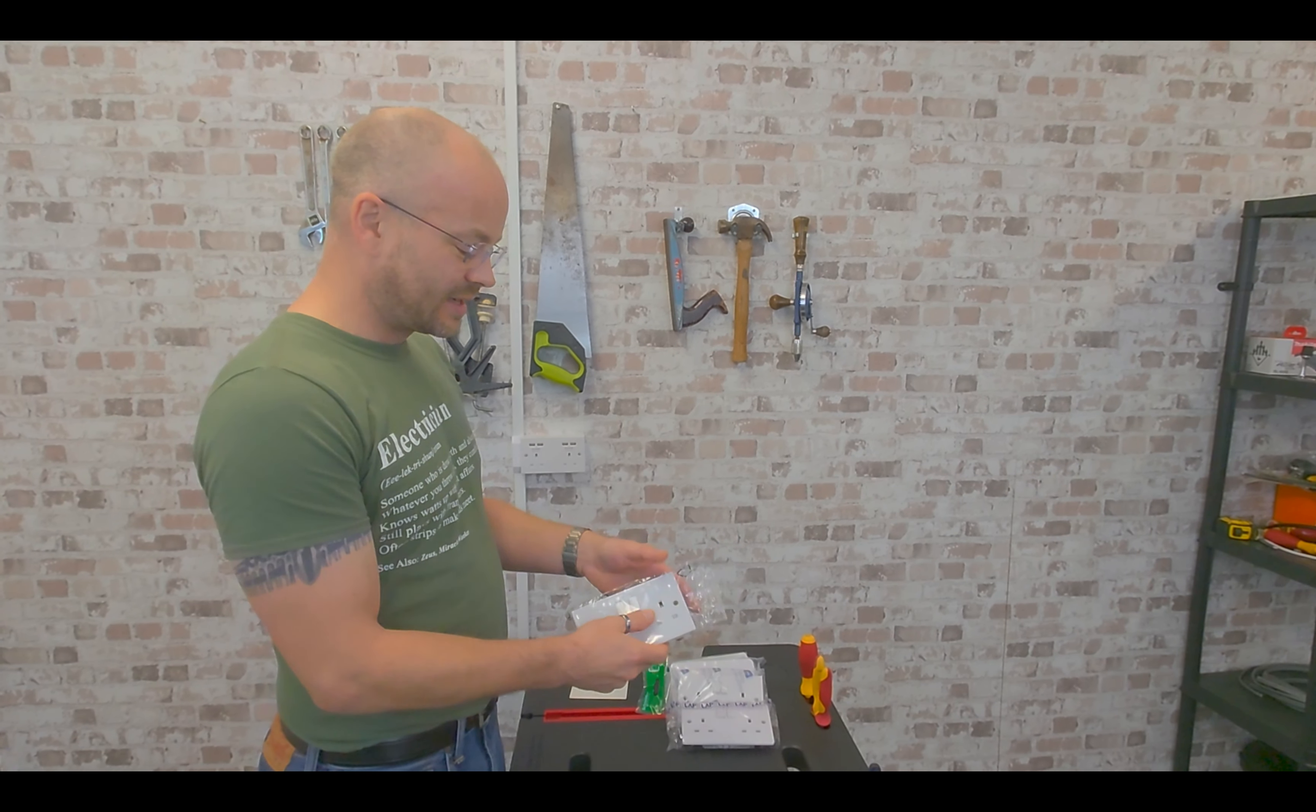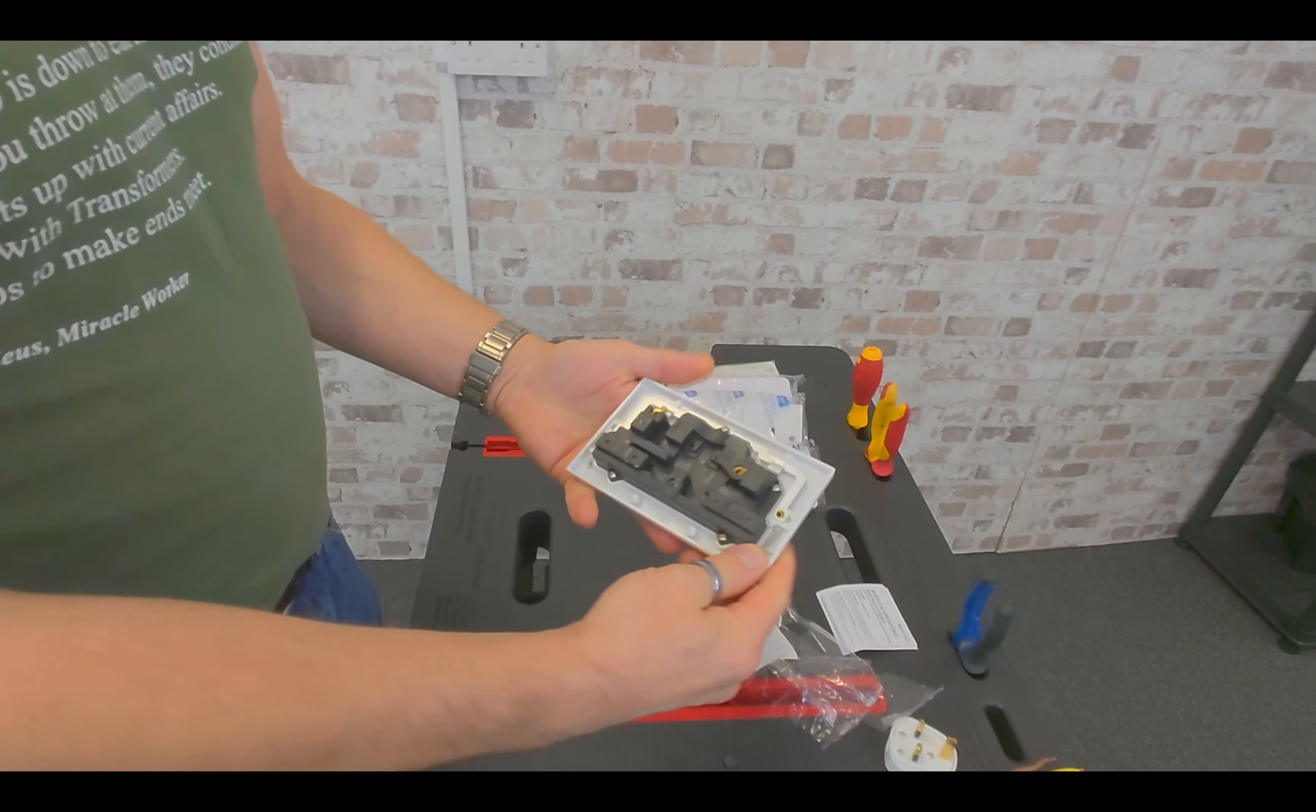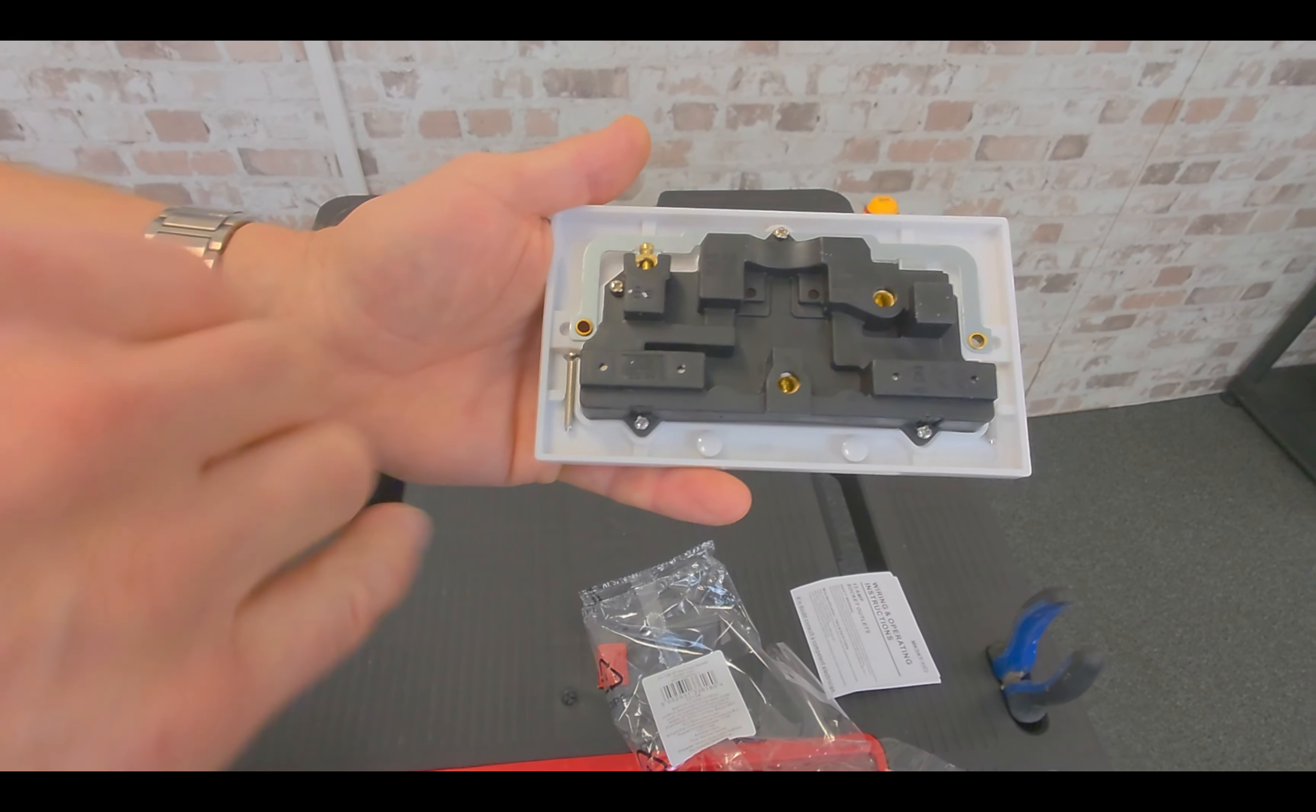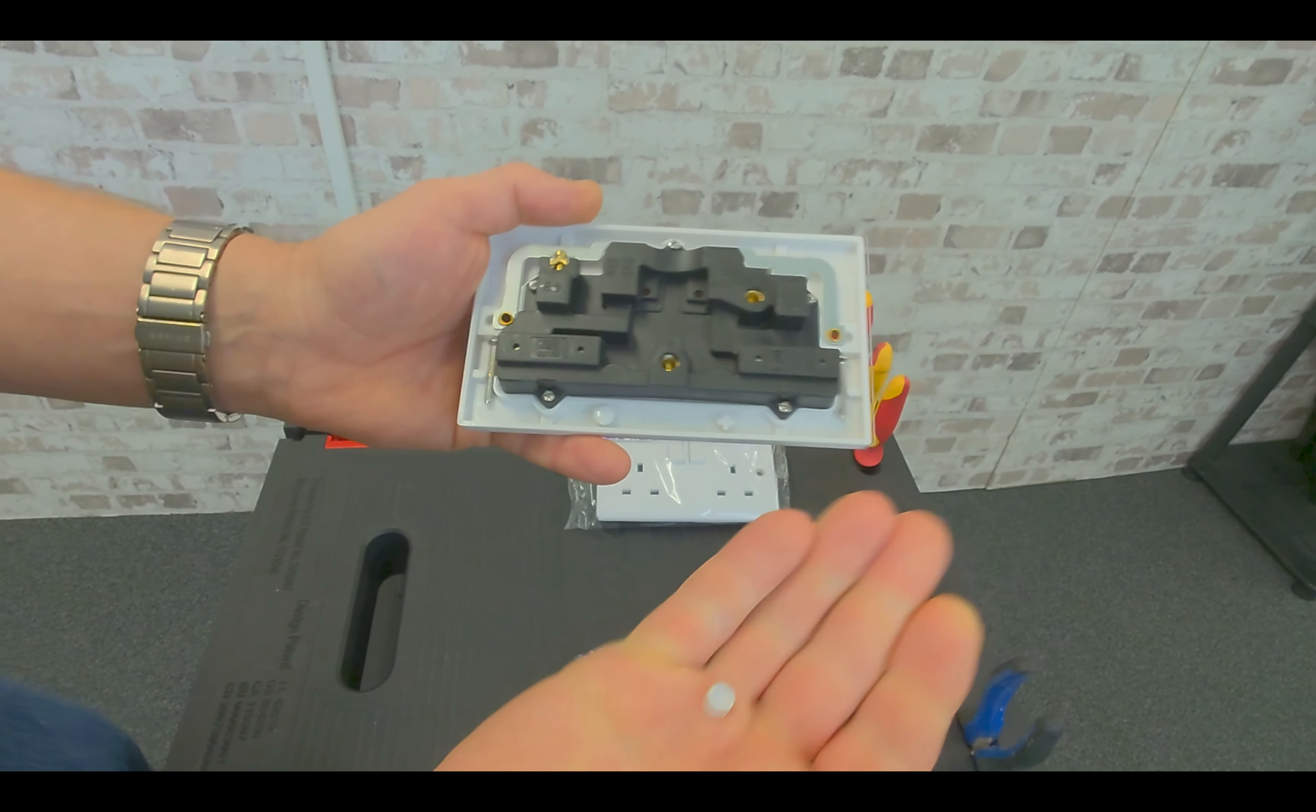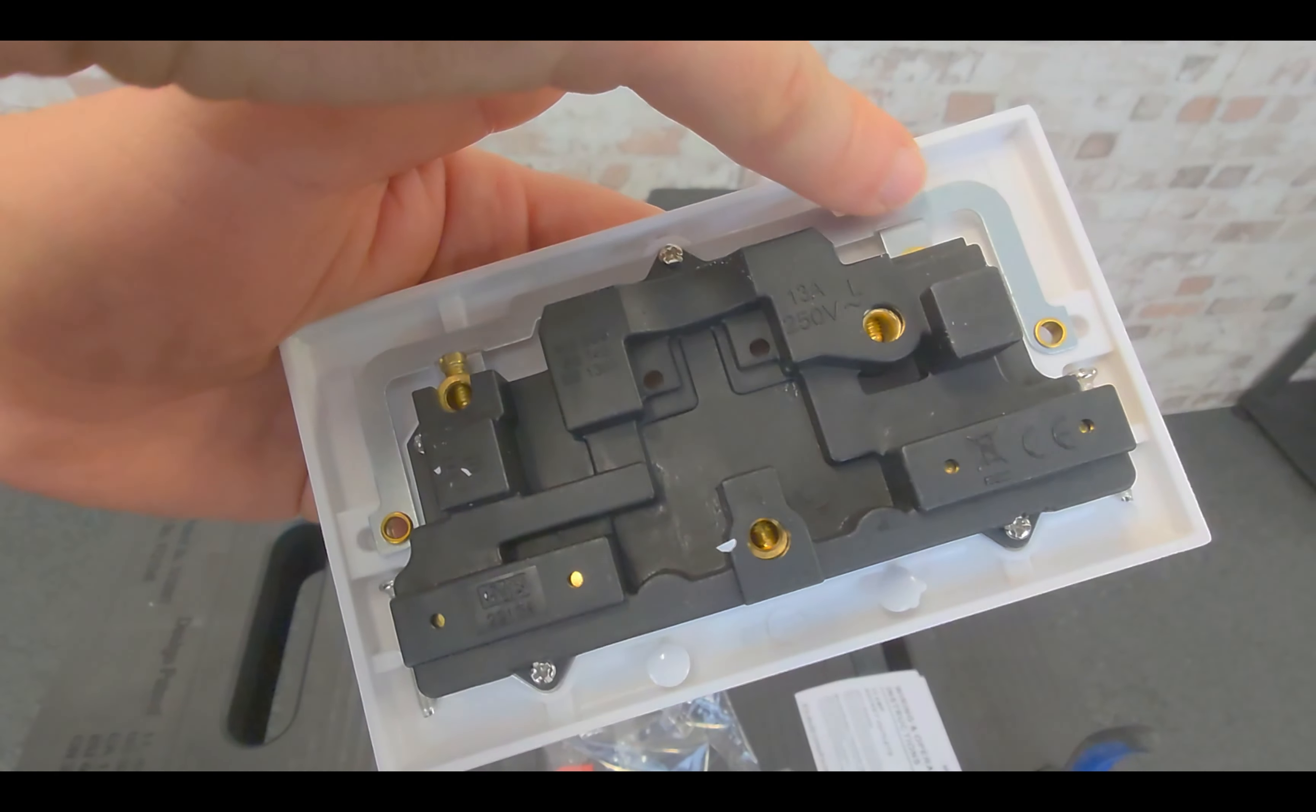So starting with the unbranded socket, you can tell straight away that packaging is also quite cheap. Let's get it open. We've got wiring instructions. Now as you can see, it's all very basic on the back. Even the plastic on the back looks quite cheap. There's no real branding on it. Now you can see here the screws are relatively short in comparison to most screws that are used for fixing these onto the walls. It has got the screw caps, which is good. But one thing notably straight away I can see is that it only has one earth, one earthing point. A lot of double sockets will usually have two, one on either side.